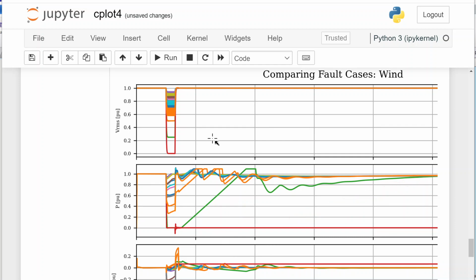That is actually for the sag down to 25% voltage. So the plant ceased to output power. The one with the 3-phase fault that took the voltage to 0, the plant went to 0 output and did not come back, but it's not required to by IEEE 2800.